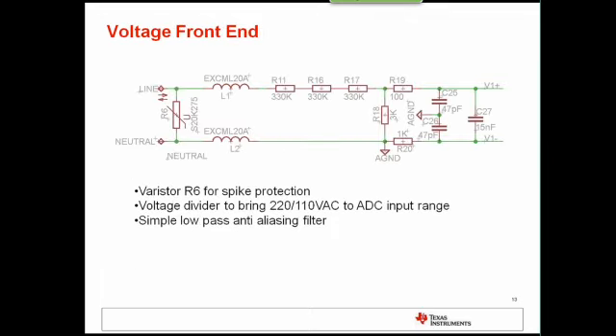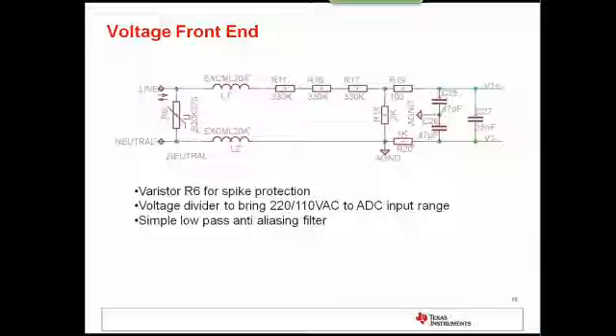And this actually shows the voltage front end on our F6736 EVM, which you guys will have a chance to play with. You have R6 as the varistor for voltage spike protection. L1, L2 are EMI filters. And you have R11, R16, R17, and R18 as the voltage divider circuitry. Basically you have a 990K resistor in series with a 3K resistor. And the reason why the 990K resistor is split into 3 different resistors is to prevent sparking. And on the front end, you also see the anti-aliasing filter.